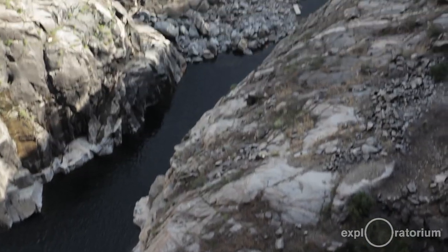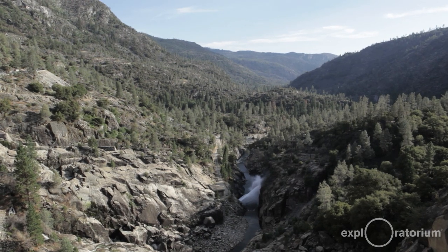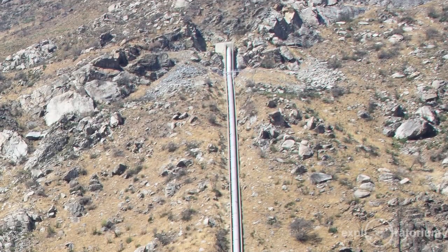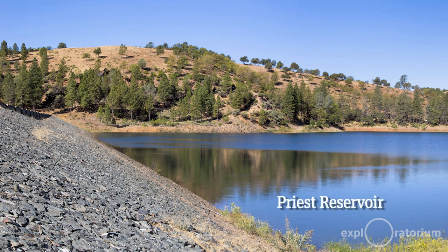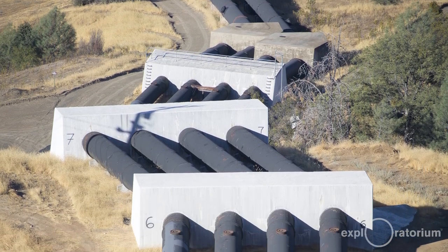The reservoir is about 320 feet deep at the dam and extends about eight miles upstream. Water leaving Hetch Hetchy Reservoir goes through a tunnel called the Canyon Power Tunnel, which carries it about nine miles downstream. The tunnel is about 12 feet in diameter, carved out of granite. It reaches a set of penstocks — pipelines that carry water down a steep hill to Kirkwood Powerhouse, where we generate hydroelectricity from the drinking water. After Kirkwood, water enters the Mountain Tunnel, about 19 miles long, carrying water down to Priest Reservoir, a regulating reservoir leading to the penstocks for Moccasin Powerhouse.